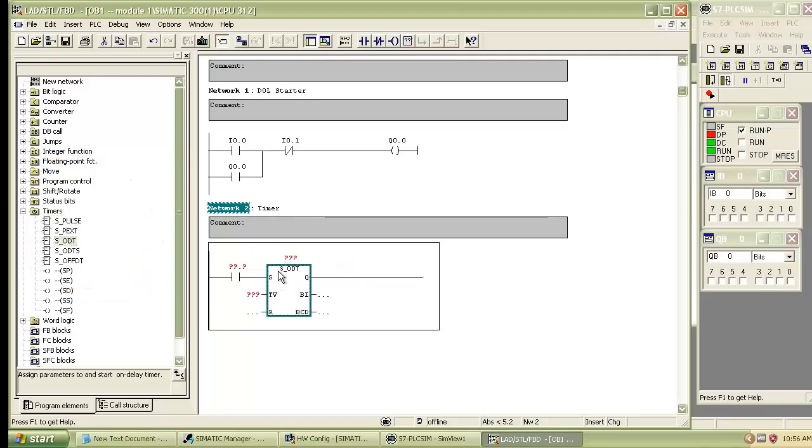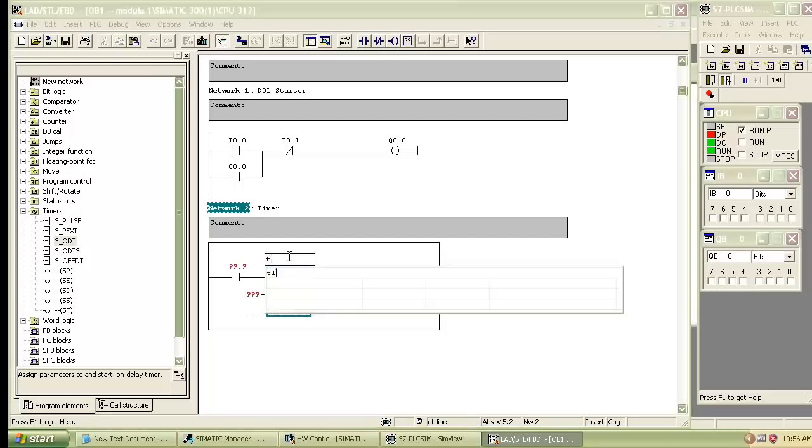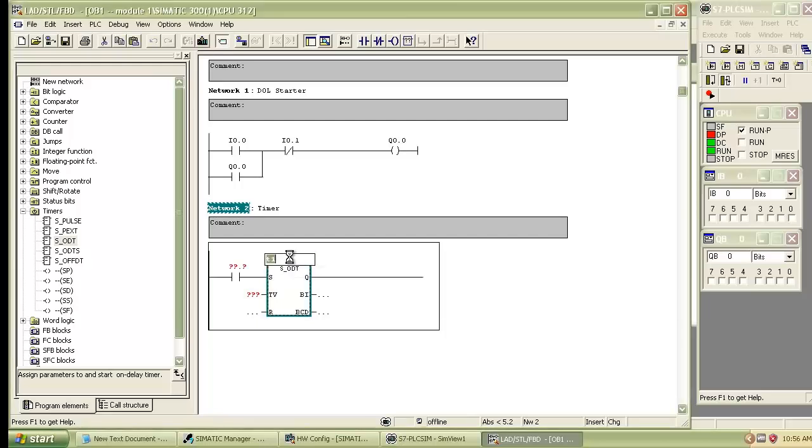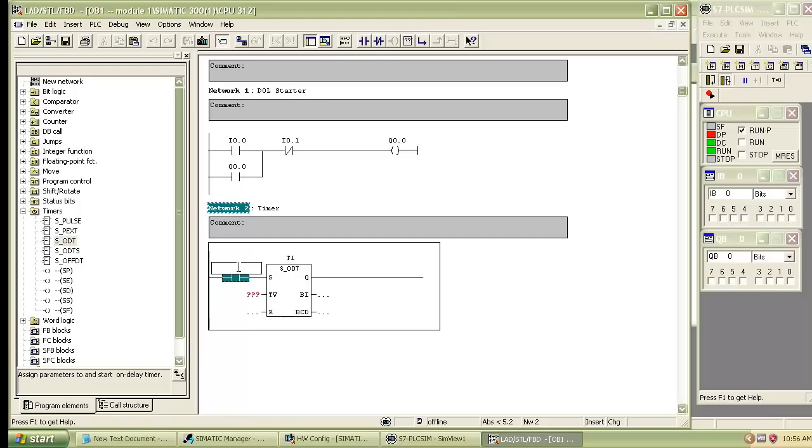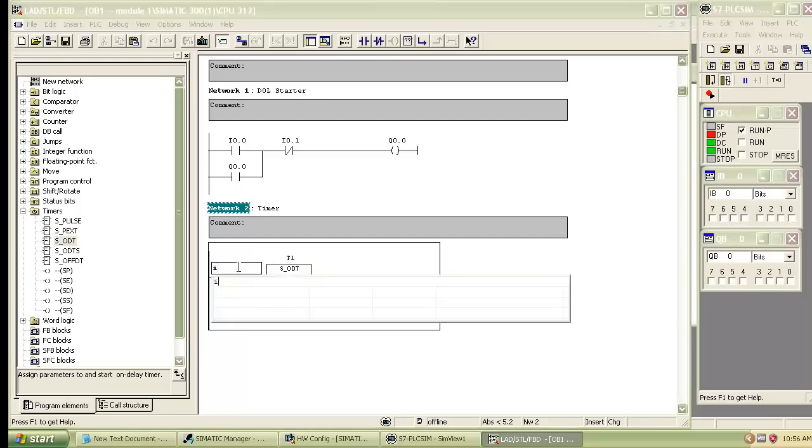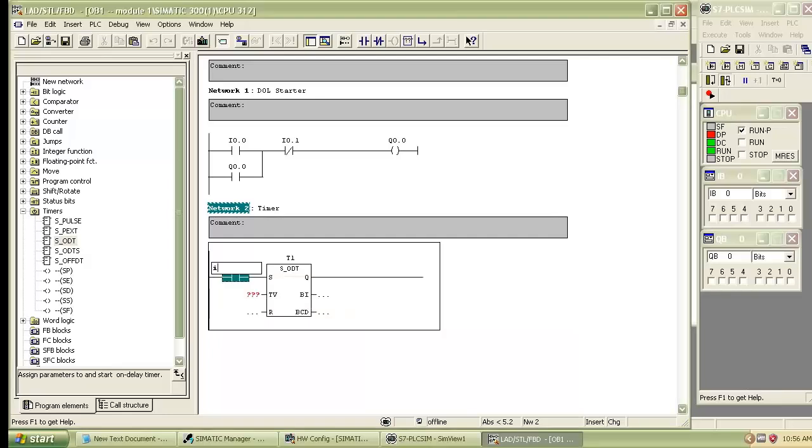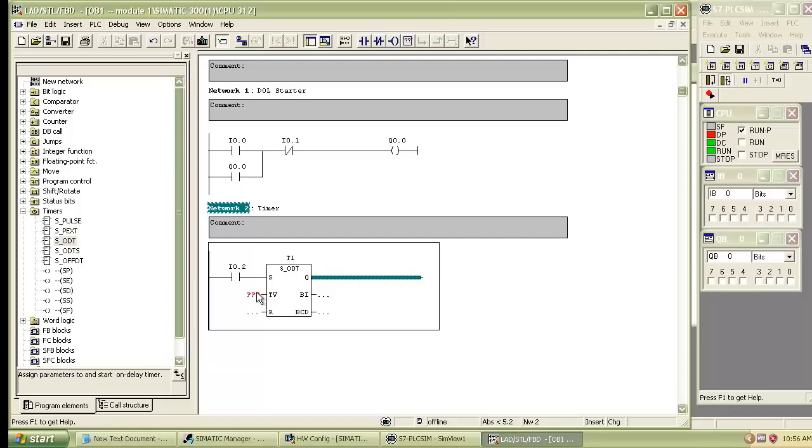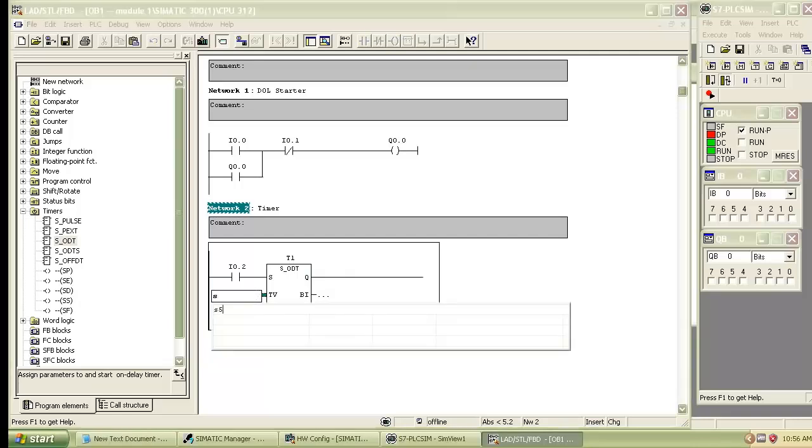Now we have to configure the on delay timer. Let's indicate the timer as T1. Then give address to the normally open contact I0.2. Then we have to give input to the timer, that is period of time for which the timer delays the output.